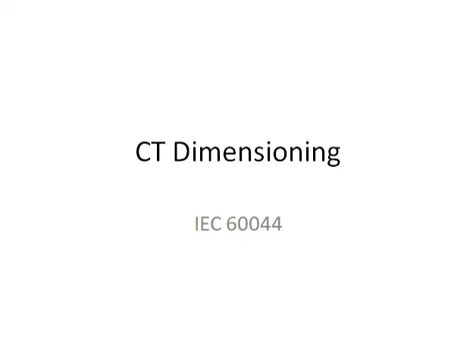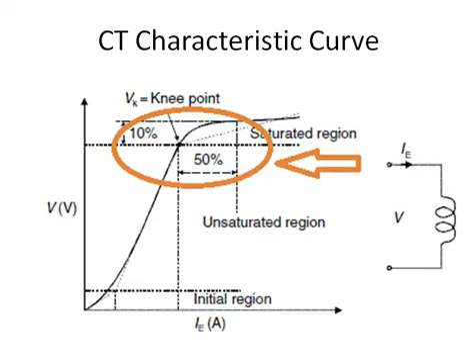Welcome to my YouTube channel Electric World Continuing Engineering. Today I am going to discuss CT dimensioning as per IEC 60044. During a transient fault condition in a power system network, if the CT gets saturated it will definitely maloperate — it will not give proper functionality. As you can see from the CT characteristic curve, up to a certain point the CT will operate properly, but after that point it will maloperate after getting saturated.